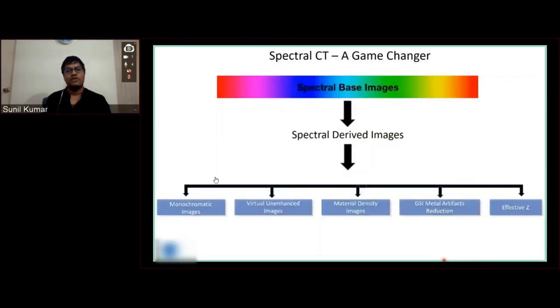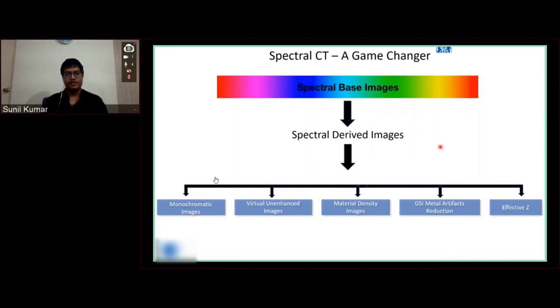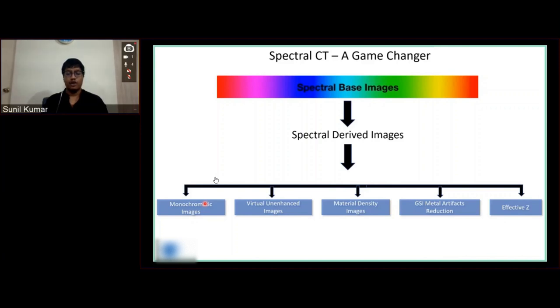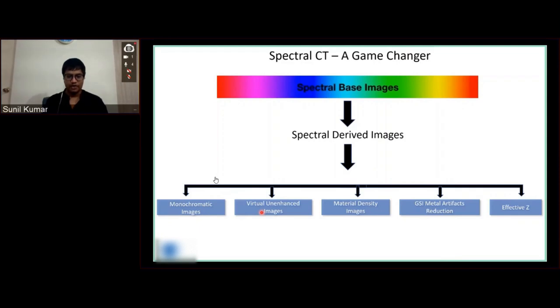Once we get the data from the detector, we call it spectral-based images. Using those spectral-based images, we can derive the following: monochromatic energy images — you can slide the values from 40 keV to 140 keV — virtual unenhanced or virtual non-contrast images, and material density-based images. You don't have to do a plain study for the patient.